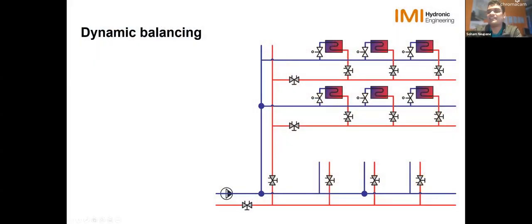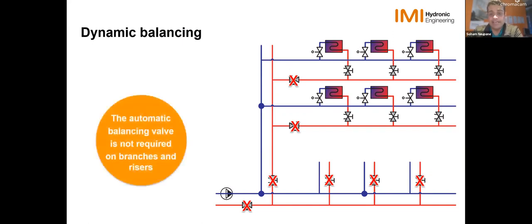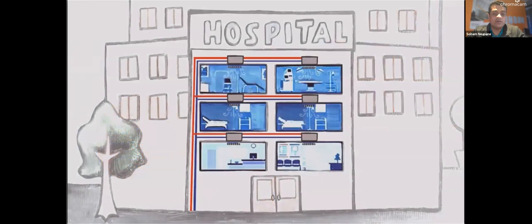So if you remember, this is the typical layout of your manually balanced building. You've got a manual balancing valve on each terminal, then you've got partner valves on your branch, your riser, and closer to the pump. So what we do different with automatic balancing is you eliminate the need for all these partner valves. When you're using an automatic balancing valve, there's no need to have any valves on your branches and risers.